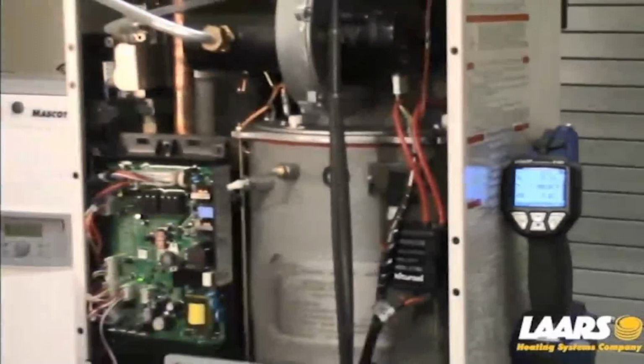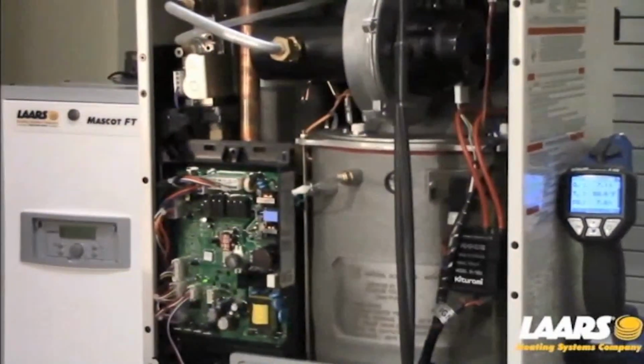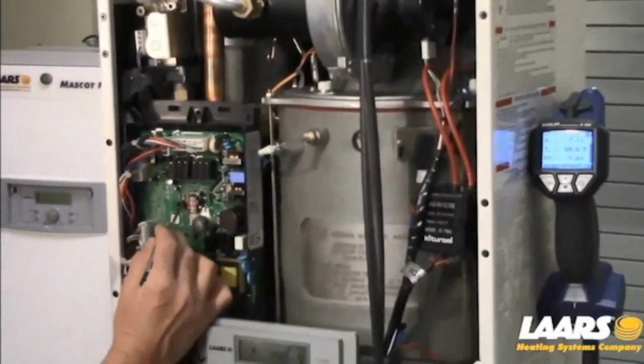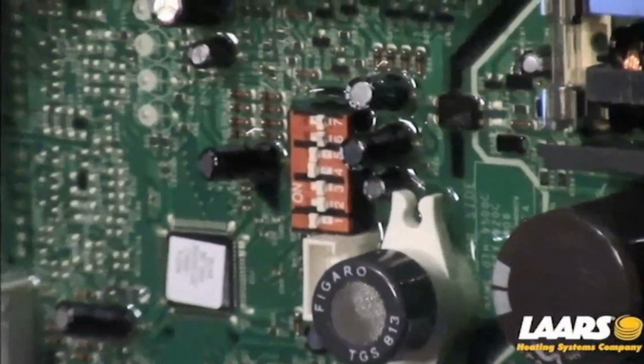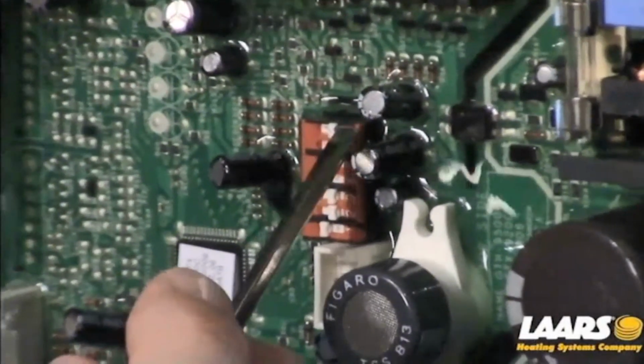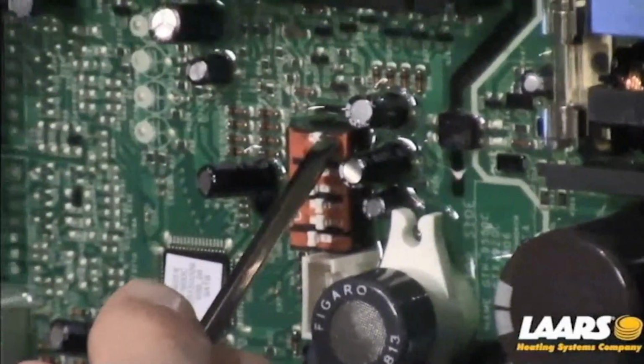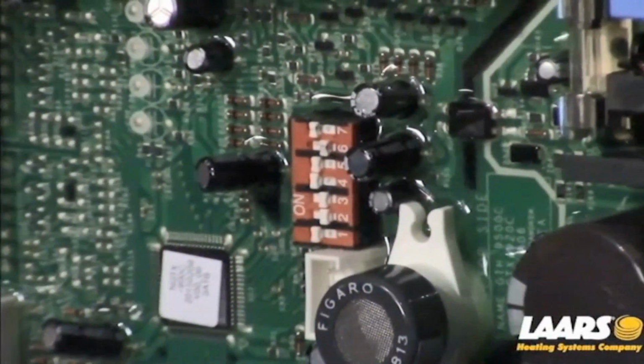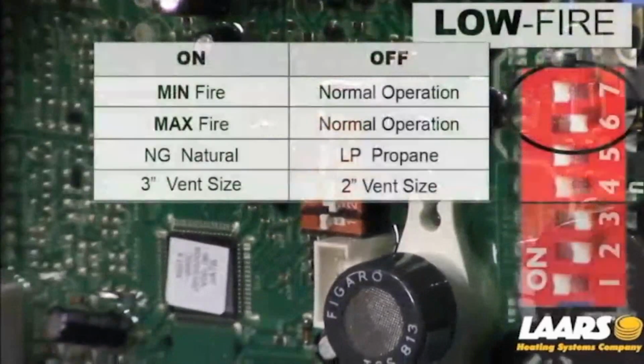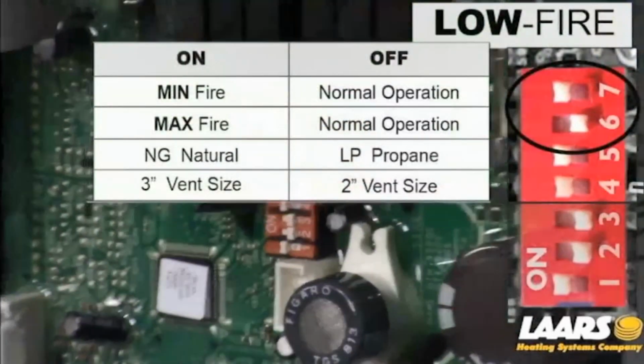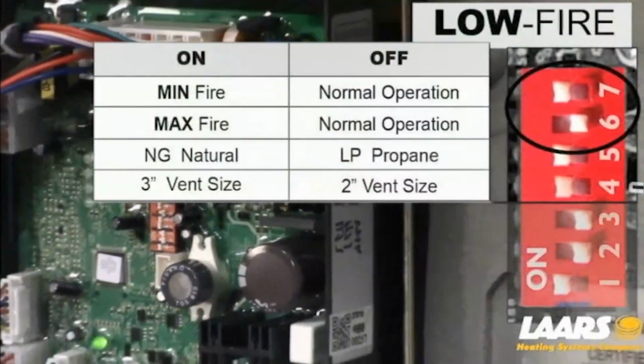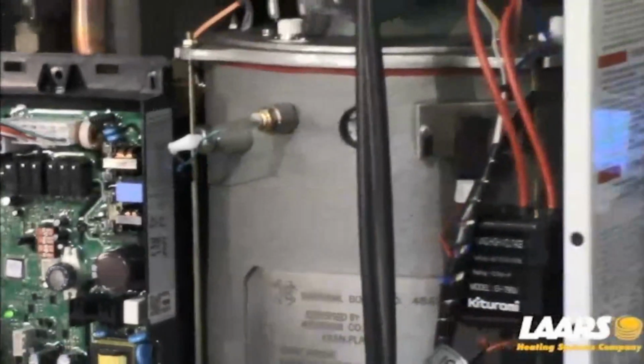All adjustments on these are made in low fire. So what we have to do is put dip switch 6 back to the right-hand position or the off position. Dip switch 7, which is our minimum fire, turn that to the on position and let the boiler modulate down. Once we're in low fire, now we can readjust our low fire setting.